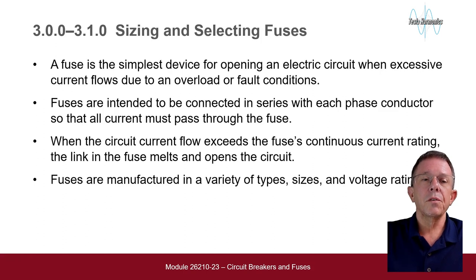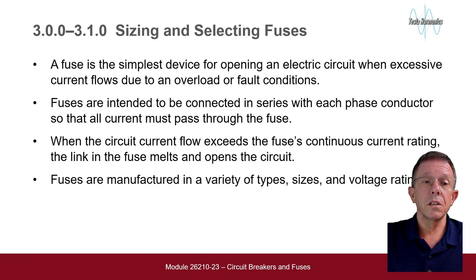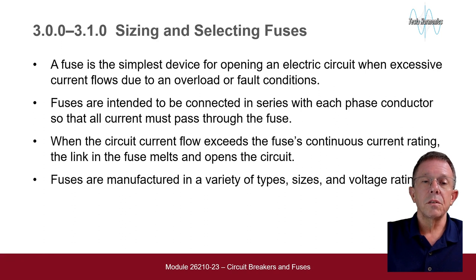A fuse is the simplest device for opening an electric circuit when excessive current flows due to an overload or fault condition. Fuses are intended to be connected in series with each phase conductor so that all current must pass through the fuse. When the circuit current flow exceeds the fuse's continuous current rating, the fusible link melts and opens the circuit. Fuses are manufactured in a variety of types, sizes, and voltage ratings.